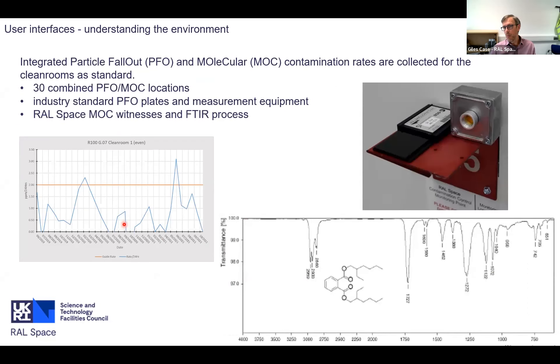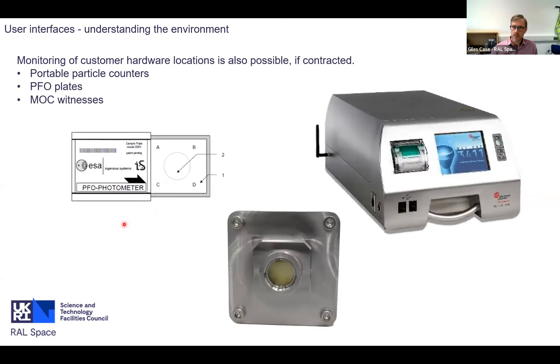Looking at historical or integrated contamination monitoring: we deploy particle fallout and molecular monitoring across all areas, with 30 combined positions in the building. We use the industry-standard ESA PFO plates with Ingenious Systems PFO meter, and our own in-house molecular monitoring witnesses and FTIR process. We can also provide this for our customers: portable particle counters placed near customer hardware, PFO plates placed around equipment, and our own molecular samples analysed in-house for a quick turnaround of contamination analysis.